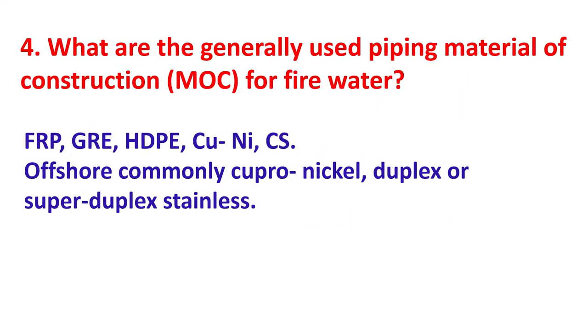What are the generally used piping materials of construction for fire water? The commonly used materials are FRP, GRP, HDPE, Cu-Nickel, CS. Offshore, commonly used materials include Duplex or Super Duplex Stainless Steel.